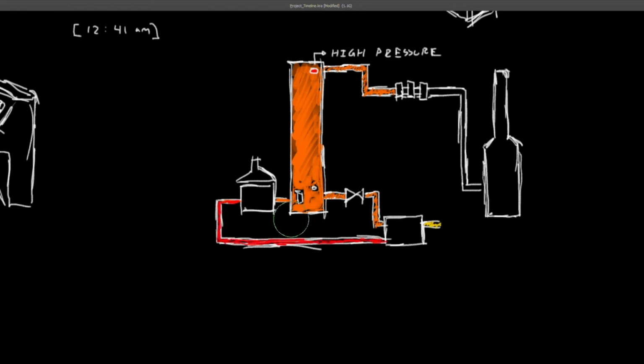The hot feed caused the liquid inside the tower to boil over, resulting in the liquid spilling over into the overhead vapor line and exerting great pressure on the emergency relief valve 150 feet above. This caused the relief valves to open and send 52,000 gallons of hot liquid to the blowdown drum. The liquid inside the blowdown drum rose far enough to begin draining into the process sewer system, setting off a second alarm in the control room.